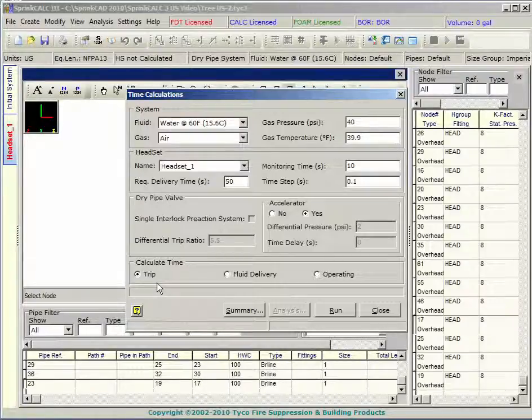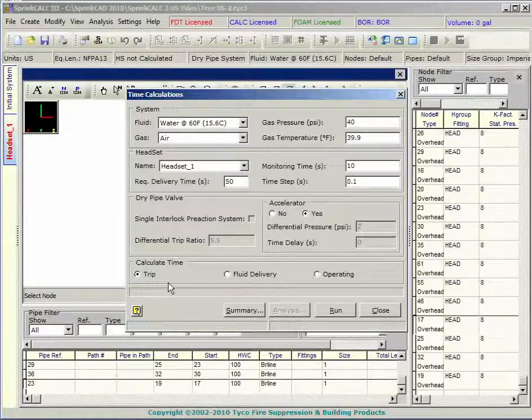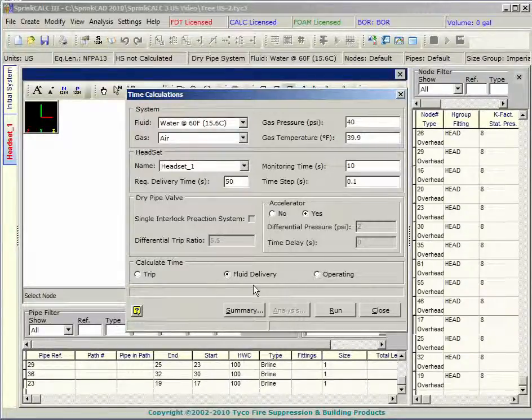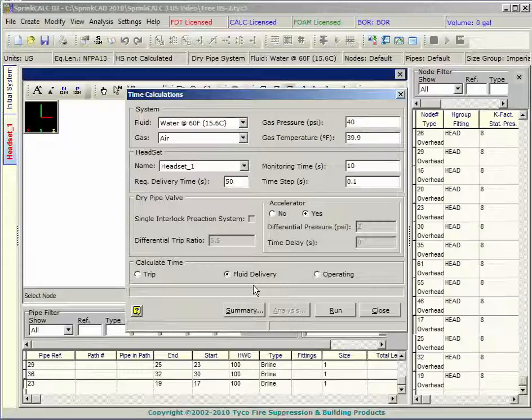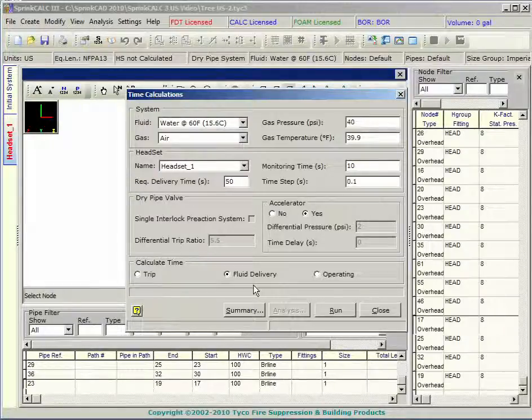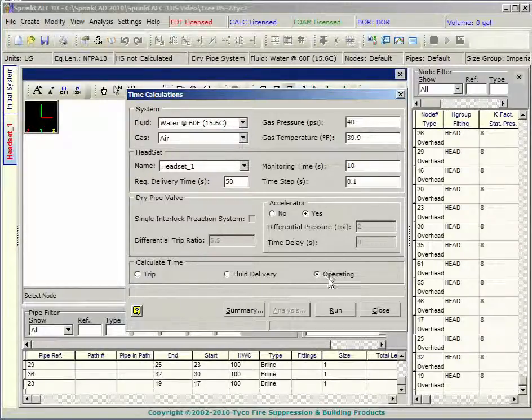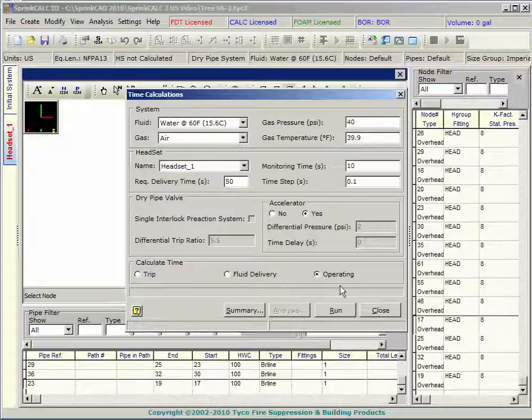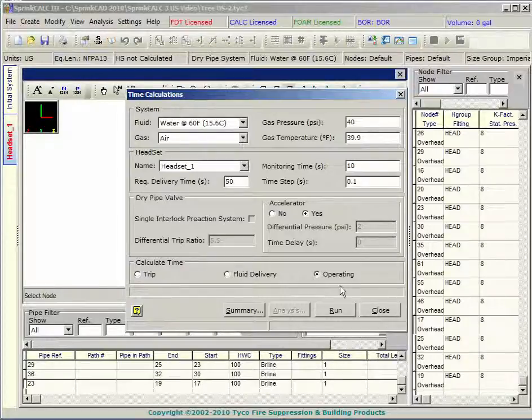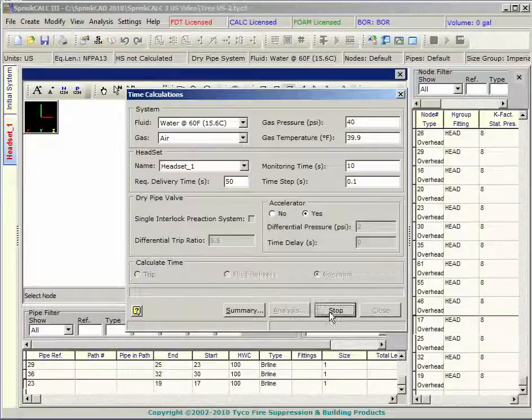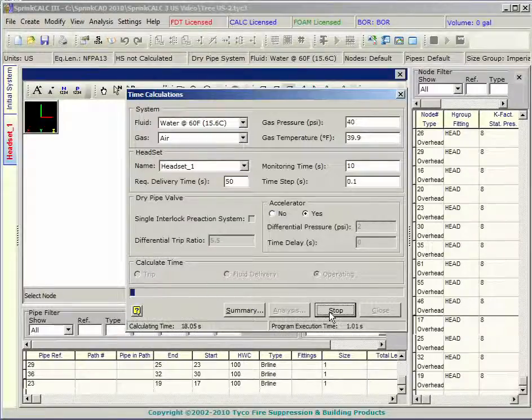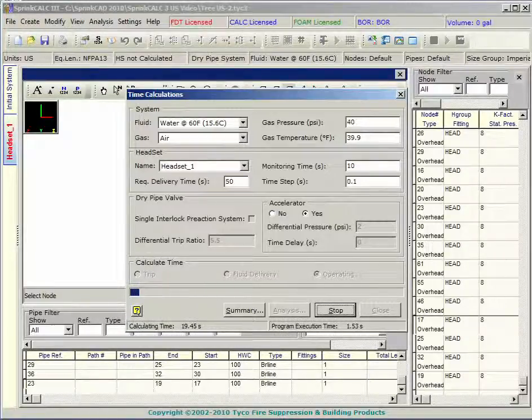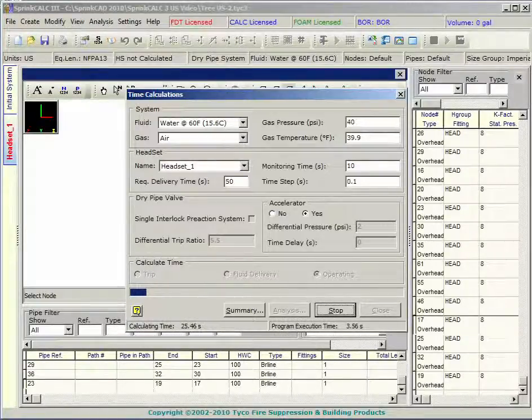Trip will determine the time for the dry valve to trip. Fluid delivery will determine the trip time as well as the time for the fluid to reach the most remote sprinkler. Operating will determine trip and fluid delivery as well as the time required for the most remote head to maintain the minimum operating pressure for the monitoring time. Press the run button to start the calculation.